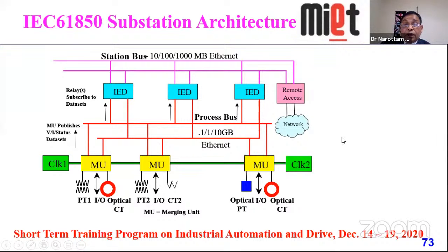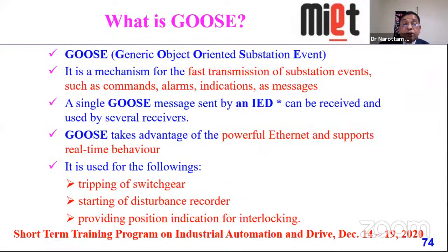Now, as I didn't discuss GOOSE yesterday - GOOSE stands for Generic Object Oriented Substation Event, and it is important because it provides a mechanism for fast transmission of substation events. If any fault or anything occurs, it should be transferred, such as any command, alarm, indication, or message.